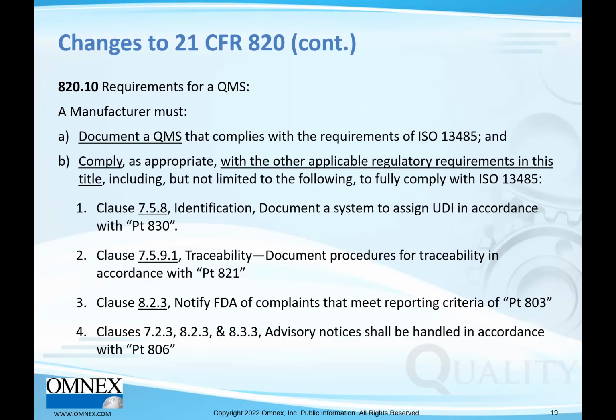Clause 7.5.9.1, the general traceability clause within 13485: the manufacturer must document procedures for traceability in accordance with Part 821. Part 821 is medical device tracking requirements. So you need to meet the requirements of that part of the Federal Register.